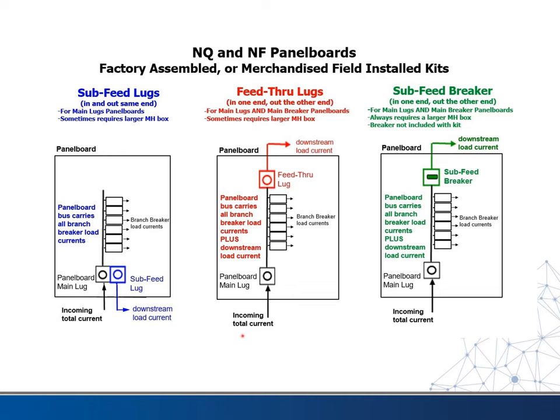So here's an example of the three things we've talked about, right? So you can have each of these three panel boards. If we come in here and put a second set of lugs here, this is called sub-feed lugs. You come in with your incoming, this will feed these breakers, and then you connect here, which is also connected to this lug, and then feed something else downstream.